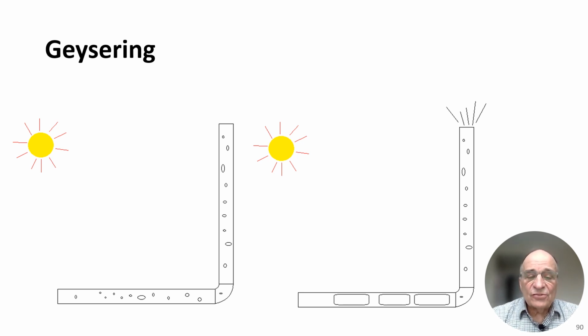Geysering is another thing you need to be concerned about. Let's say you have a horizontal leg and a vertical leg that's filled with LNG. And heat leak into that LNG causes bubbles to form. Once bubbles form in this vertical leg, what happens to the pressure at the bottom of the vertical leg? It becomes less. Why? Because the bulk density of this liquid is less, and therefore all of this liquid in here starts to see a lower pressure. And once that starts to see a lower pressure, it generates vapor, and this is an accelerating event that can push that vapor and liquid out of the pipe at a very high velocity, which can cause thermal stresses at the connection point at the top of that pipe.